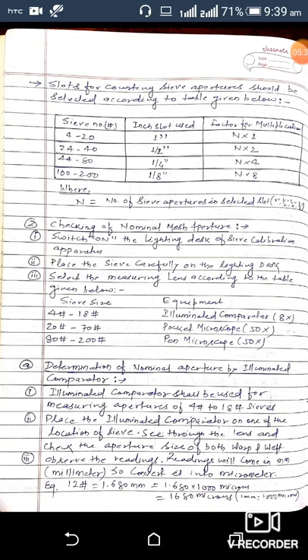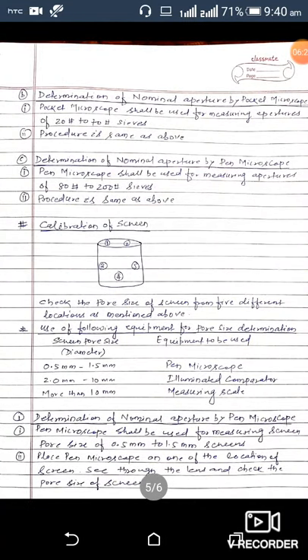Determination of nominal aperture by illuminated comparator: the illuminated comparator shall be used for measuring aperture of 4 mesh to 18 mesh sieves. Place the illuminated comparator on one of the locations of the sieve, see through the lens, and check the aperture size of both warp and weft. The reading will come in mm; convert it to micrometers. For example, 12 mesh = 1.680 mm, multiplied by 1000 = 1680 microns.